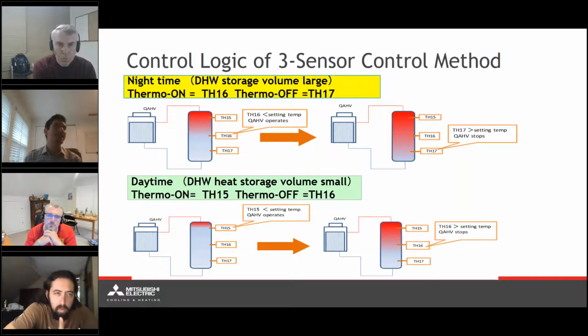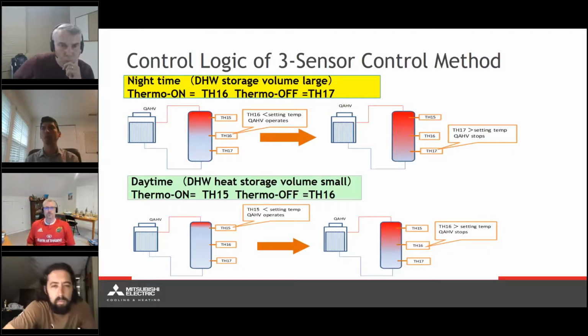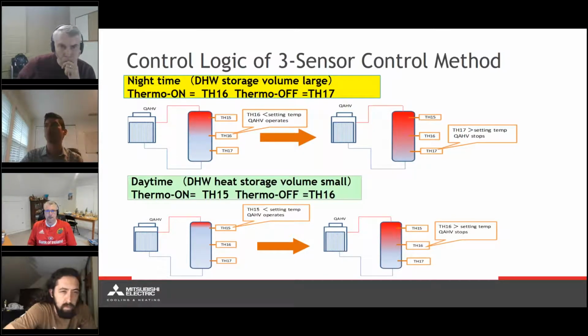So ultimately, nighttime is when the QAHV is going to be doing the bulk of its supply of hot water to the storage tank. In this particular instance, on the top left here, we have the trigger to turn on the QAHV when the middle temperature sensor drops below a specific set point. That way we know that less than 50% of our tank is achieving our minimum set point temperature within the hot water tank. At that point, the QAHV will turn on, and it will run until the temperature sensor furthest to the bottom achieves the set temperature necessary, in which case the heat pump will turn off. So when all 3 temperature sensors are registering water temperature above the set temperature, that's when we know the whole storage tank is at appropriate volume and appropriate temperature.